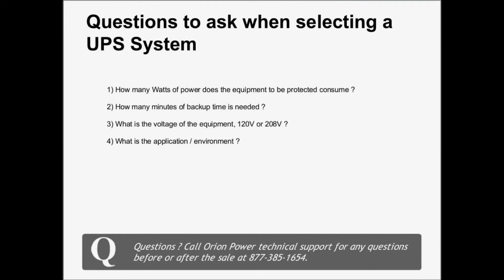Okay, so what are the questions to ask when you're selecting a UPS? Essentially, how many watts of power does the equipment consume? You would get your wattage information on each piece of equipment, add it up, and that would be your total load. How many minutes of backup time is needed? That's really going to be up to the end user. And then, what's the voltage of the equipment? We see 120 and 208 all the time. It just depends on the application. And then, what's the application and the environment? Most UPS systems are designed to be used indoors in a climate-controlled environment, so that's going to have a great effect on the life expectancy of the UPS system.